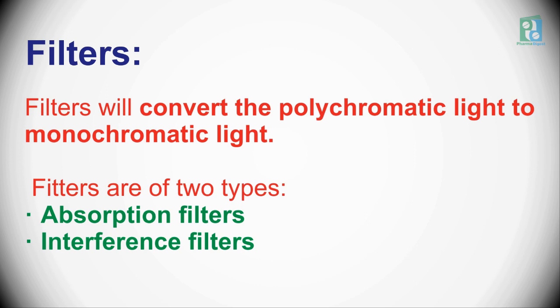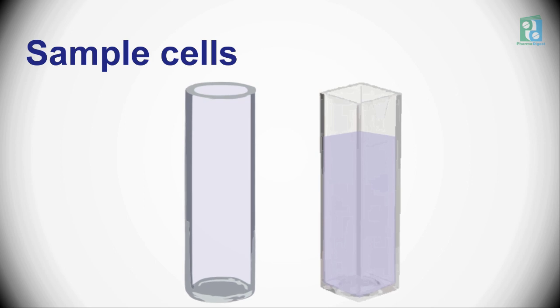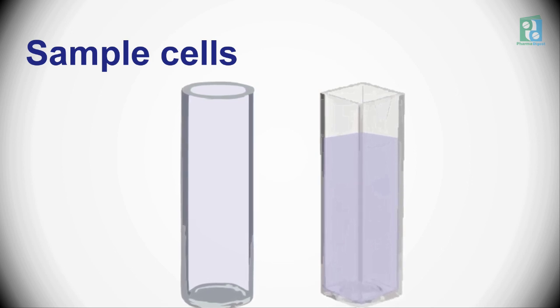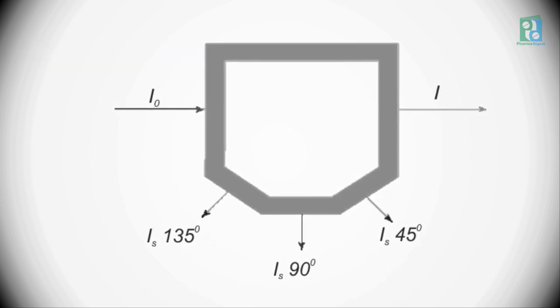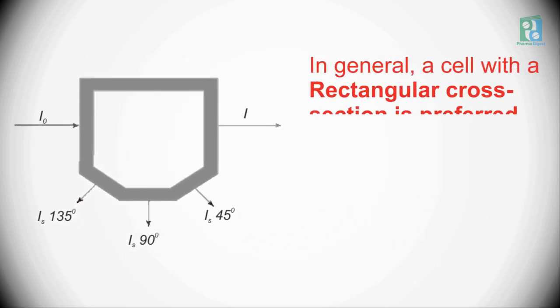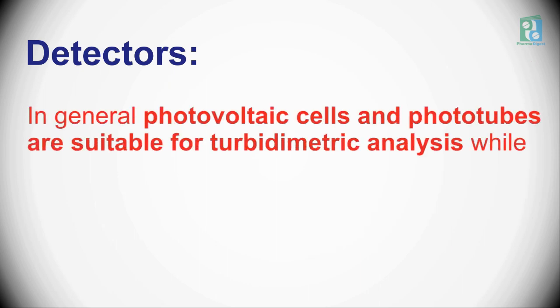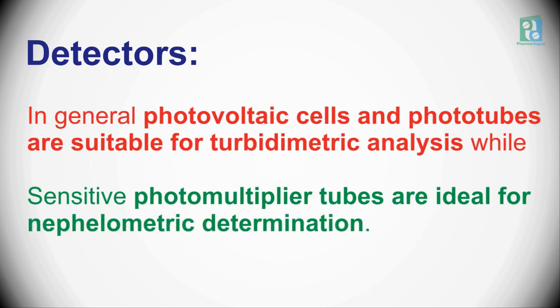Filters are of two types: absorption filters and interference filters. Cuvettes or sample cells are used to hold the sample under interest and are generally made of transparent glass. Geometrically they may either be cylindrical or rectangular in shape. A cell with a rectangular cross section is preferred where measurements are to be made at angles other than 90 degrees. Semi-octagonal cells are widely used. Photovoltaic cells and phototubes are suitable for turbidometric analysis, while sensitive photomultiplier tubes are ideal for nephelometric determinations.